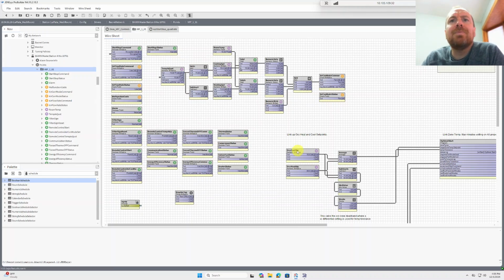Okay, so I can see that this VRF system has a set point here of 73, and they're doing some kind of deadband under the hood. Maybe they've gotten this VRF system to work this way, but I can see they have some heating and cooling set points, and there's also this occupied start, or the start command.